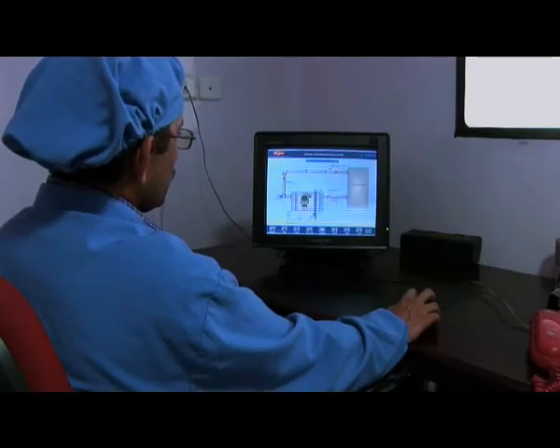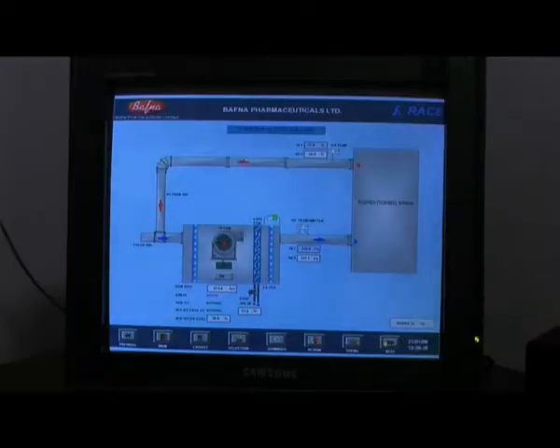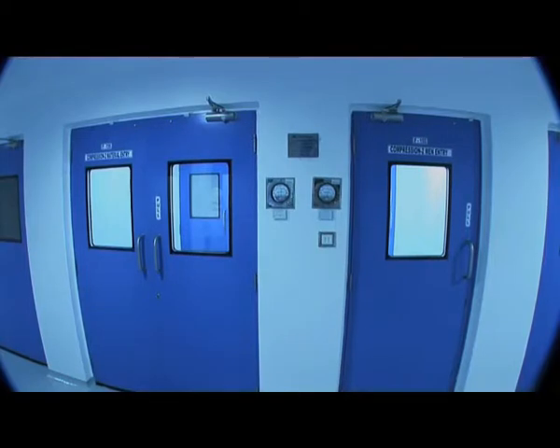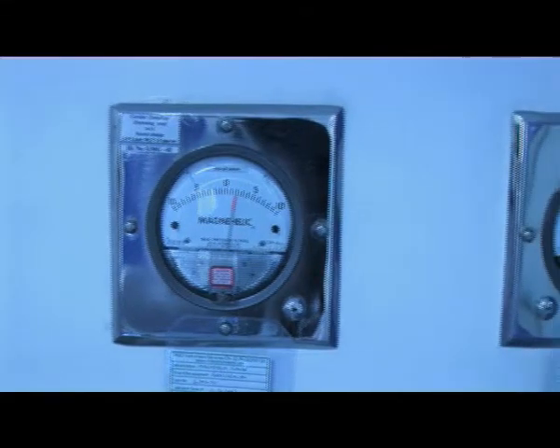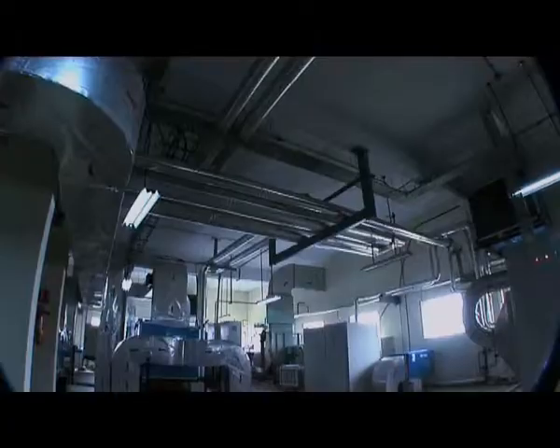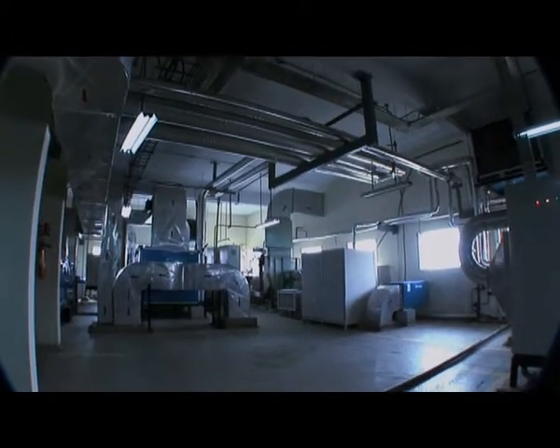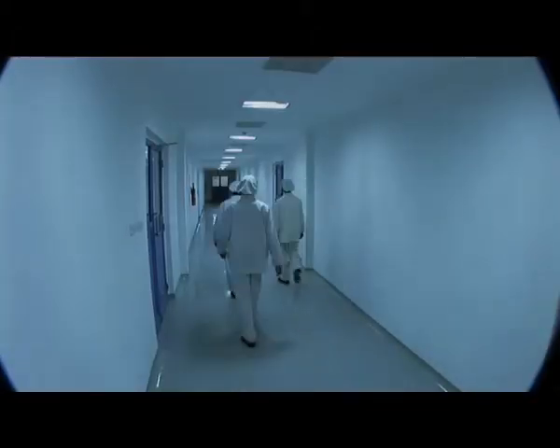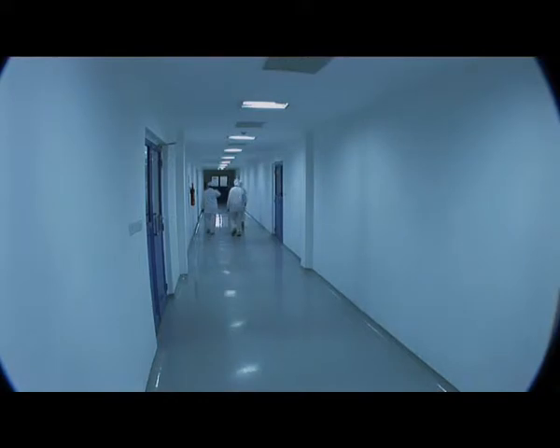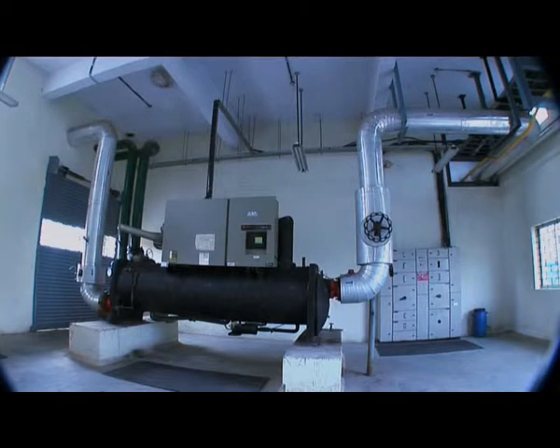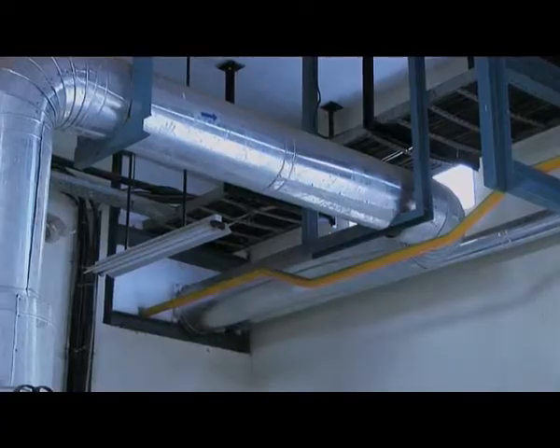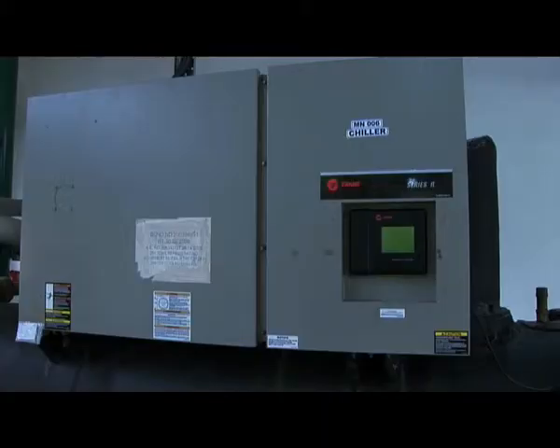Bafna takes extreme precautionary measures to ensure total control of temperature and humidity. Equipped with a 22 HVAC system, HEPA filters and a 90% recirculatory capacity, the entire plant is kept below 25 degrees Celsius for hygiene and sterilization. Chilled water circulated at 5 degrees Celsius from the screw chiller with a capacity of 260 TR controls the temperature.